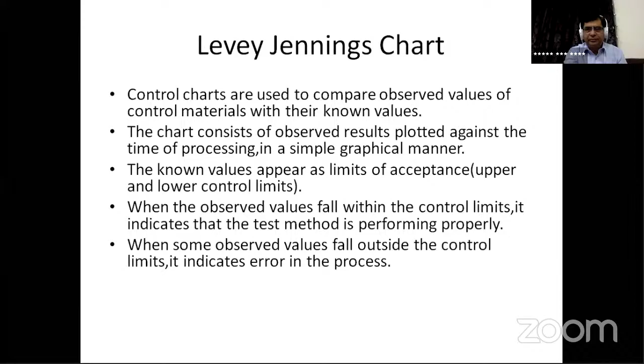The control charts or Levey-Jennings charts are used to compare observed values of control materials with their known values. The chart consists of observed results plotted against the time of processing in a simple graphical manner. The known values appear as limits of acceptance, or upper and lower control limits. When the observed values fall within the control limits, it indicates that the test method is performing properly. On the other hand, when some observed values fall outside the control limits, it indicates error in the process. We'll define these errors and discuss how to correct this at a later stage.